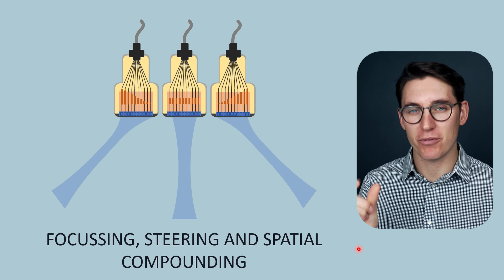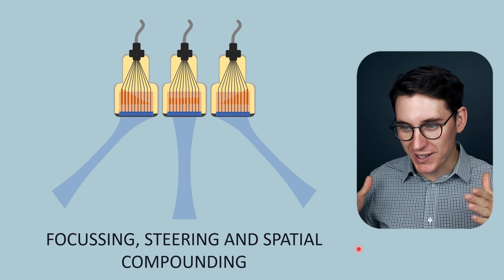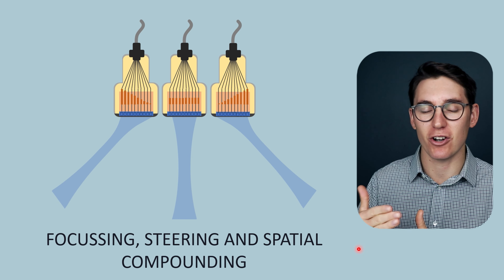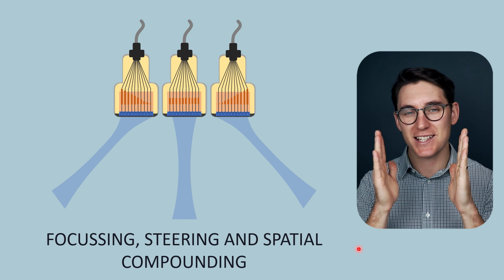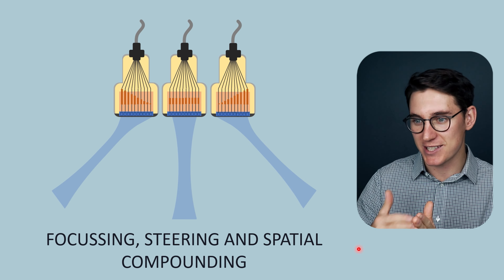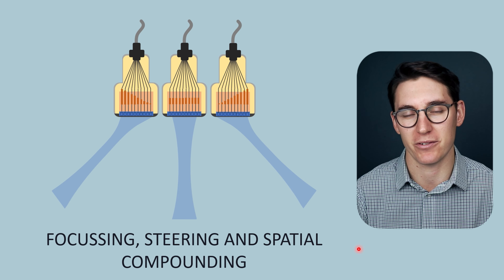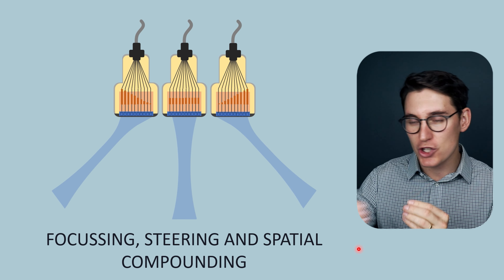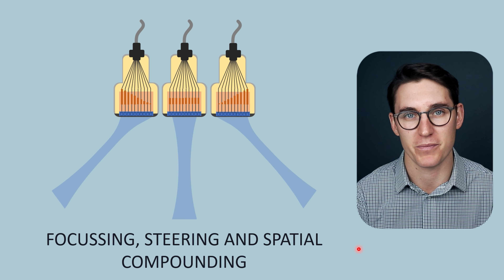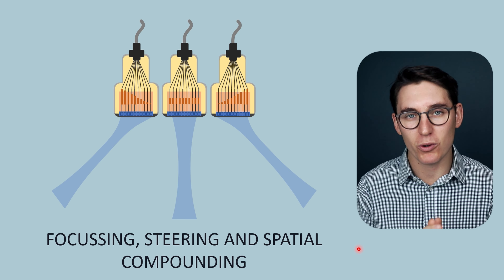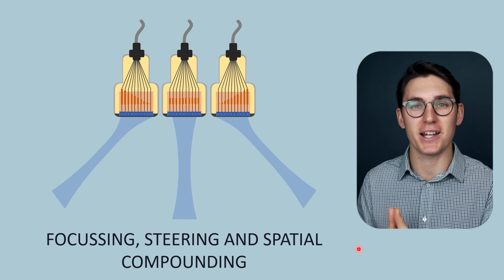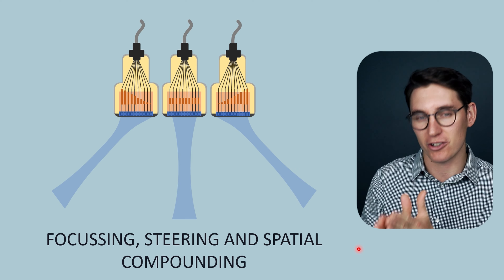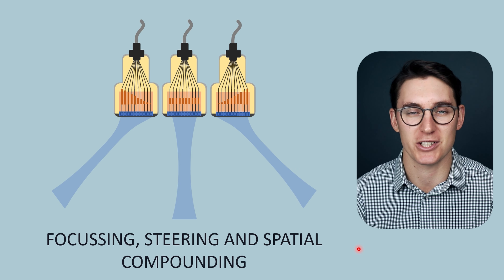We've seen that the depth of the focal zone within the ultrasound beam is determined by both the frequency of the ultrasound pulse as well as the diameter of the transducer elements creating that ultrasound wave. In this talk we are going to look at other mechanisms we can use to change the depth of our focal zone, and also how we can manipulate the ultrasound beam to change the angle of inclination as it travels into tissues.